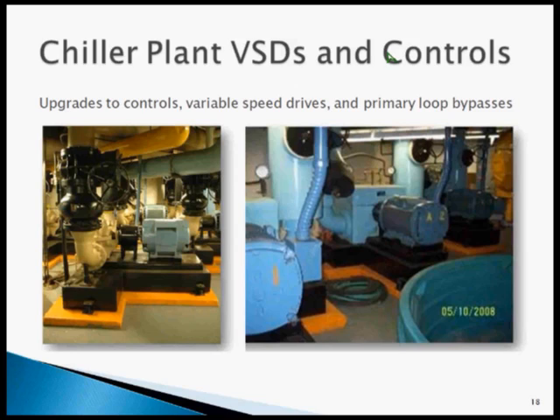Let's look at two-way valves throughout the system in the air handling units or your loads. Let's just say you have a stamping plant or pultrusion or whatever you've got, whatever the loads of chill water, hot water, let's go ahead and let that system go down to whatever's needed. We'll put a variable speed drive on the pumps. Those make a ton of sense, okay? I wouldn't go crazy with variable speed drives on every little motor in the building, but those two that I just mentioned, very, very strong.